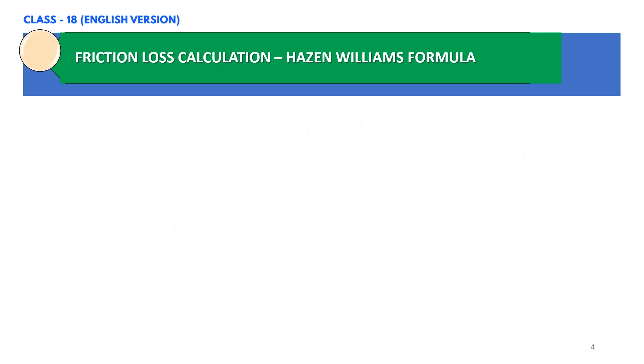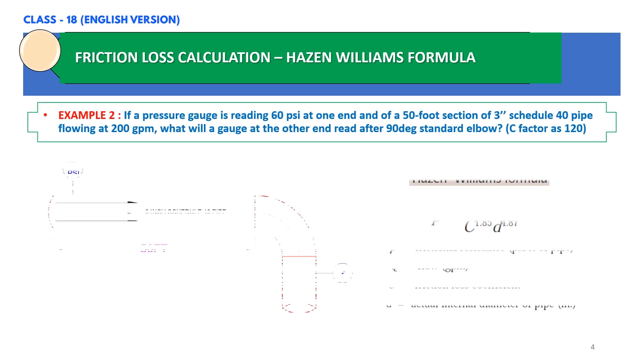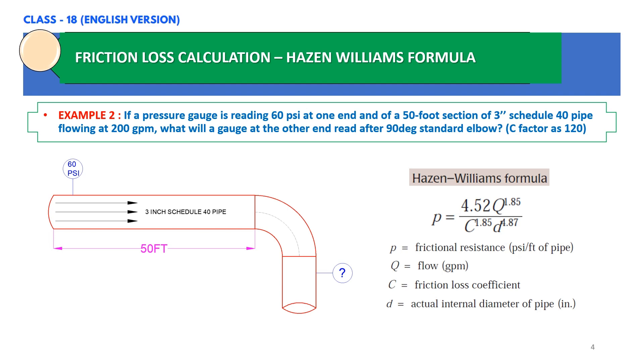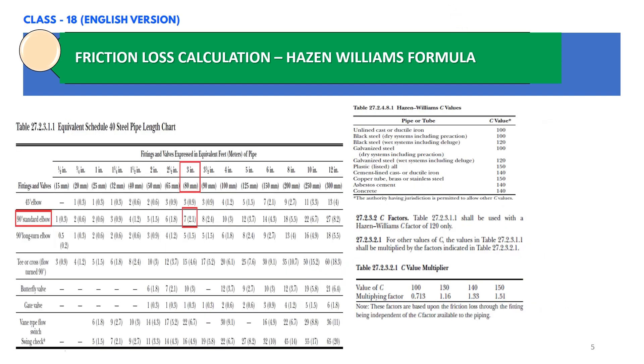Now let's look at our second example, which includes one elbow along with the straight pipe. We shall calculate the pressure reading after the elbow. As per NFPA 13 Table 27.2.3.1.1, we have an equivalent schedule 40 steel pipe length chart. In our example we have a 90-degree standard elbow, and for a 3-inch pipe the equivalent length from this chart is 7 feet.